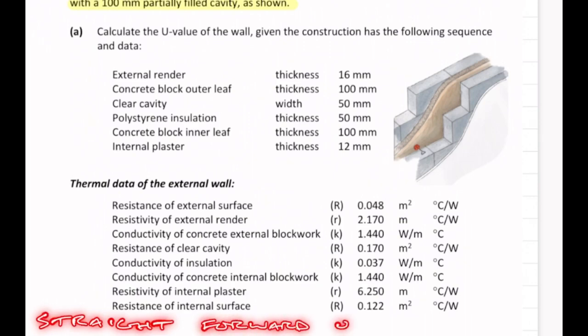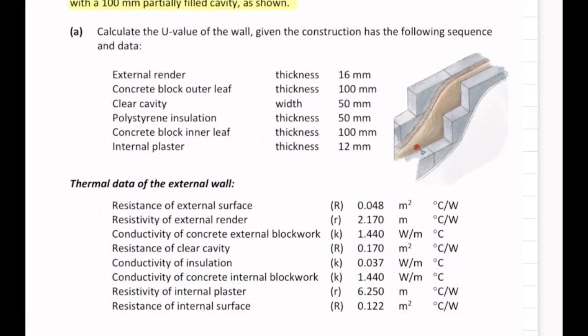So the table is the same as it always is. It's a 5x5 grid, so I do 5 centimeters by 5 units, and the reason it's 5 centimeters is just because it's handy to remember 5 by 5. And in those grids are the material element, conductivity, resistivity, thickness in meters, and the overall resistance. With that overall resistance, which is the resistance total, we divide 1 by the resistance total, which gives us our U value, which you'll see later.